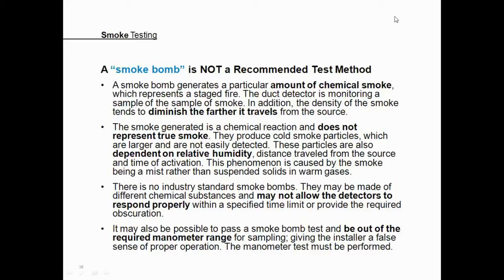The particles produced by a smoke bomb are larger than those created by an actual fire, and they are also what would be called cold smoke particles instead of warm smoke particles. And the cold smoke particles are typically not known to be as easily detected.